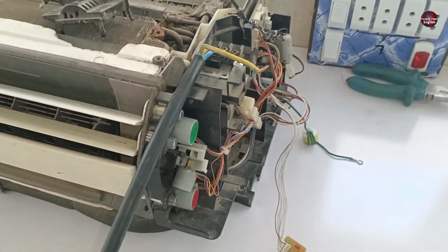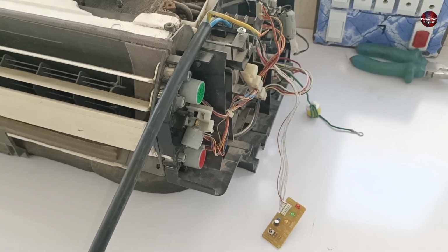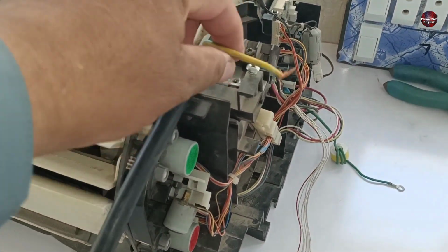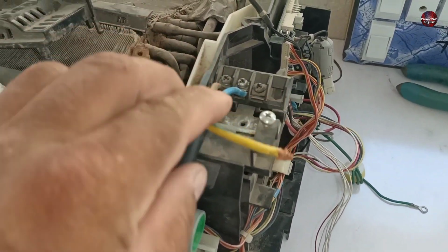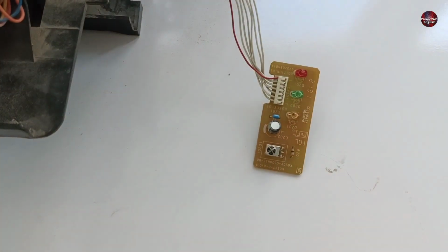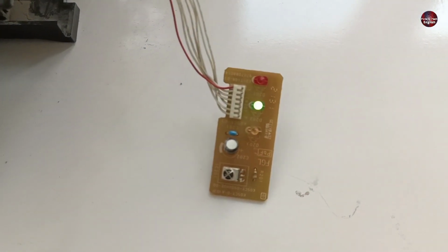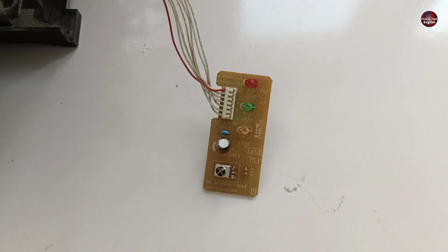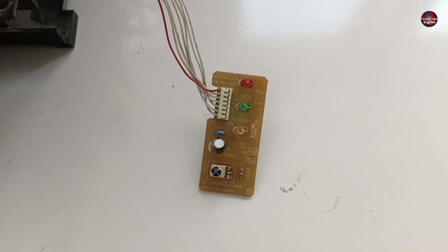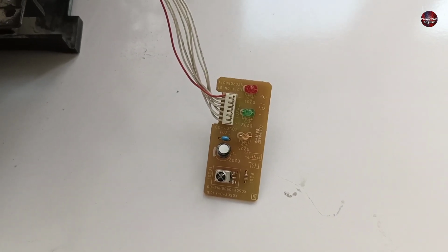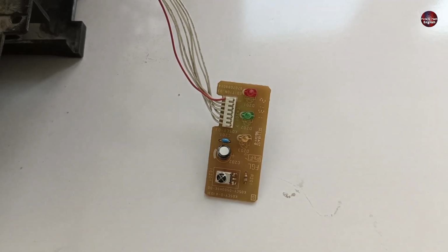Now, to explain whether this indoor unit is a first, second, or third edition motherboard, I didn't attach the communication wire to the indoor unit. Let me show you what error it shows now. The timer light is blinking two times, which confirms through this error code that the motherboard in the indoor unit is the second edition.